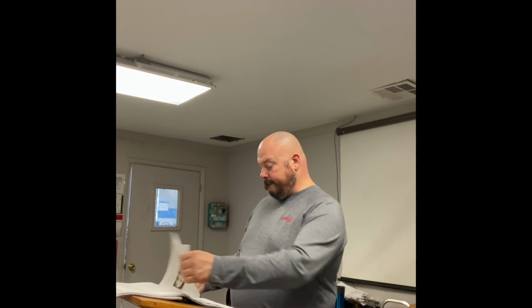Picture 1 is the compressor. Picture 2, the one on the right hand side, that's the head. You can see where the valves are slapping the top of that head. Okay. Next picture is a scroll compressor. It is blown up. Here we're talking about the one side stays still. This is the side that stays still, and the whole wall of that is. Next picture, Jerry. Yeah. That whole wall is completely broken down on that scroll compressor.